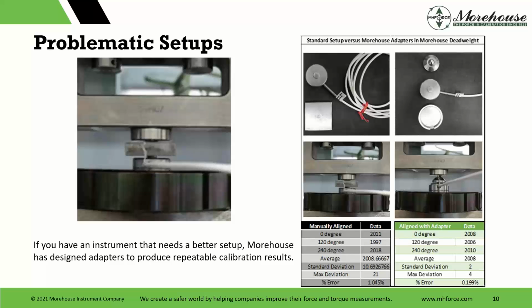So I was talking about flat to flat versus using the right adapters. Here's a problematic setup. This instrument comes into the lab and we use it. We do the calibration, and you can see here, I'm going to go back to my pen and drawing tools. This is on the left. And what we're looking at is when we did this cal, look at the deviations. And we rotated the load cell around, and then we had such large deviations. The standard deviation was 10.69 pounds of force, maximum deviation of 21, and an error related to that of 1.045%.